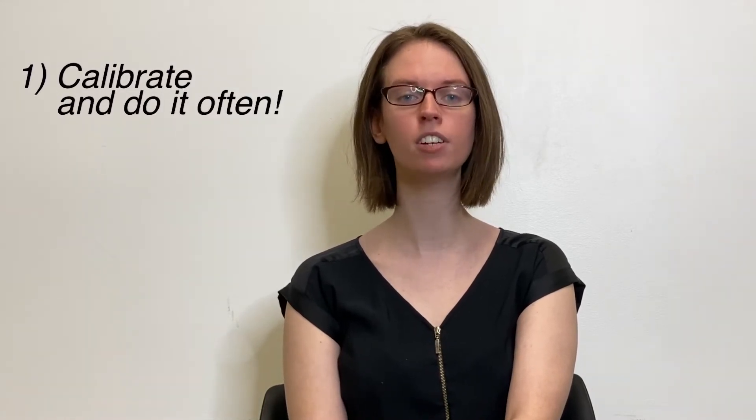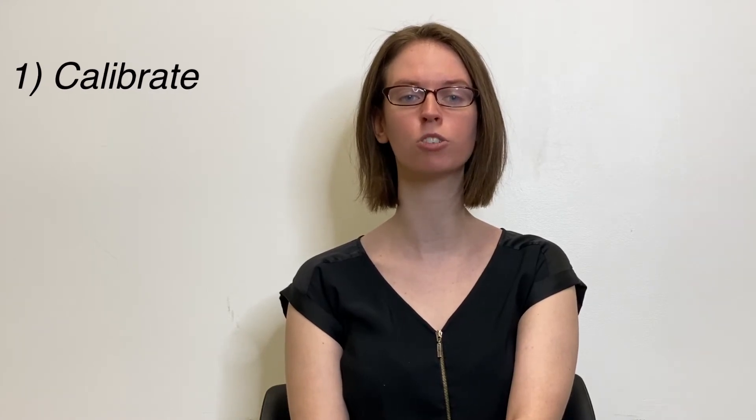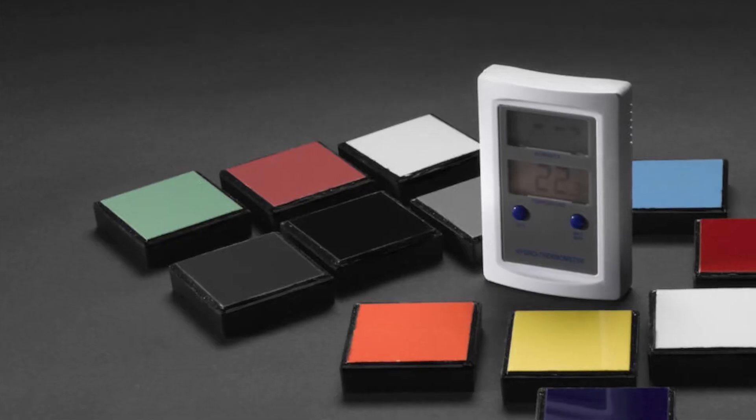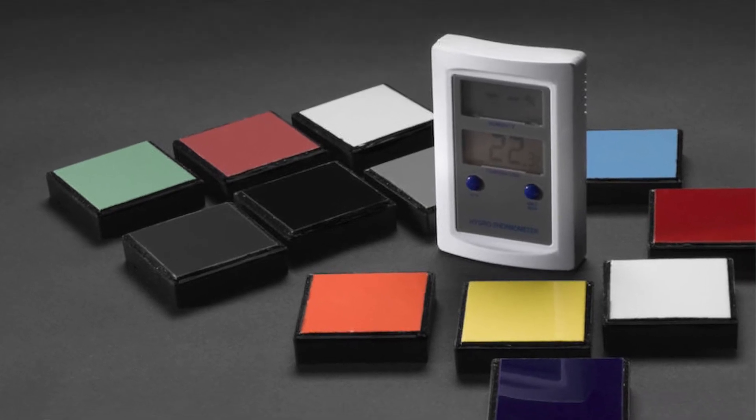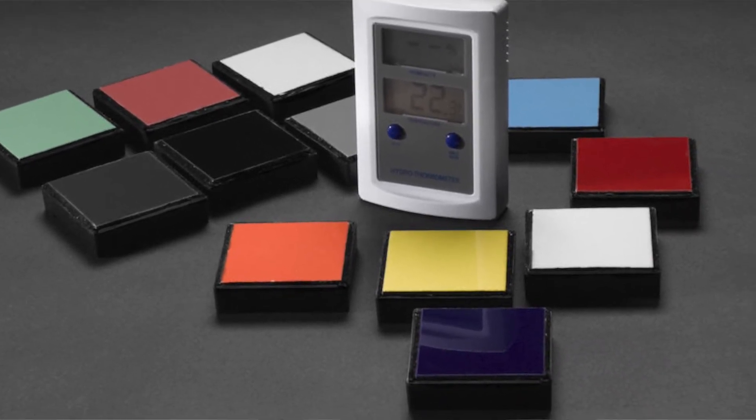Rule number one, calibrate, and do it often. Even if the manufacturer only recommends that you calibrate your spectrophotometer daily, consider recalibrating every two to four hours, and immediately before particularly important jobs.